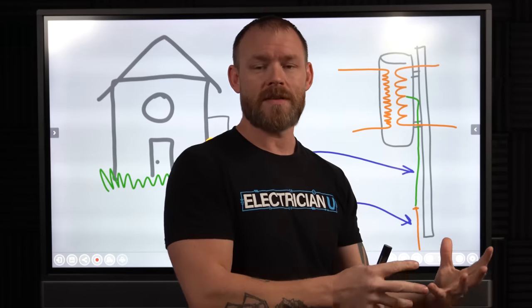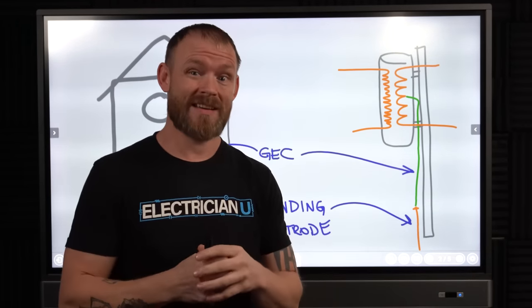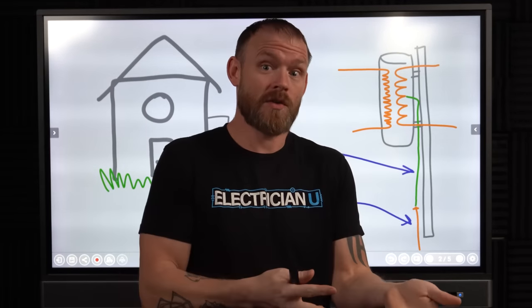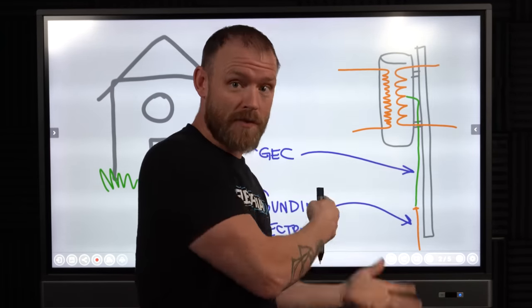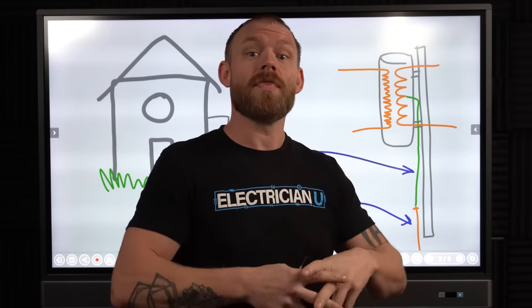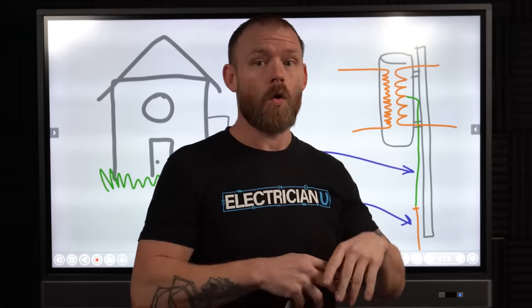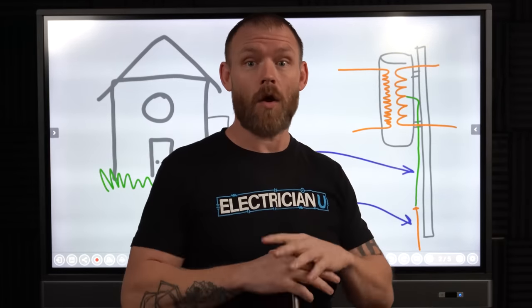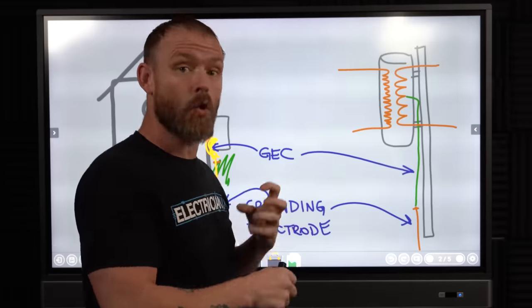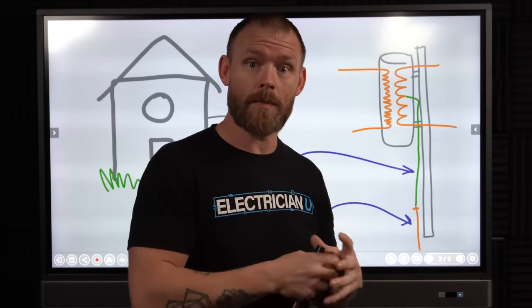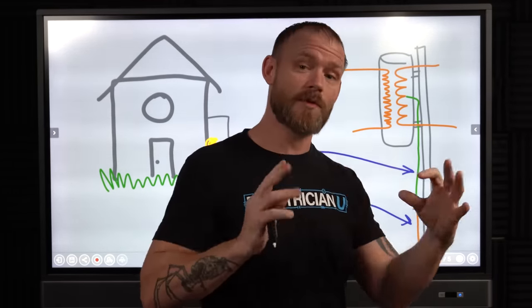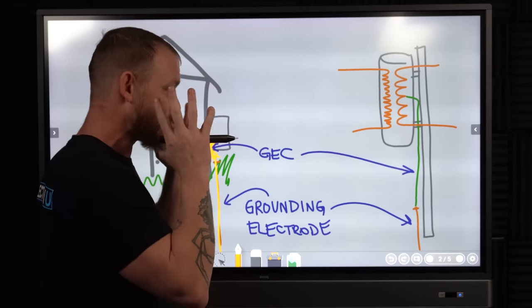Grounding electrodes were not always installed. In old school wiring systems it was just a hot and neutral — there was no ground as a reference to earth, and the systems worked just fine. With clearing faults, it's a completely different thing. Equipment grounding conductors and bonding conductors are what are actually used to trip breakers. So keep those things separate in your mind.